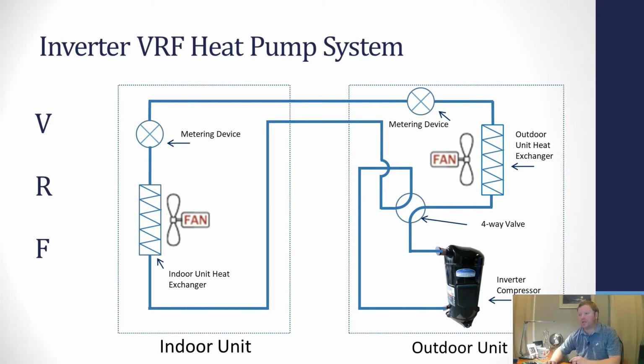capable of. So as we discussed last time, when you have a VRF heat pump system, we add that second electronic expansion valve at the indoor unit, and it has a ton of advantages. But one of the biggest advantages is your room temperature control, because now when I have multiple indoor units, I can have each indoor unit's expansion valve throttling totally separate directly at the indoor unit, which helps a ton with the refrigerant flow through the heat exchanger.